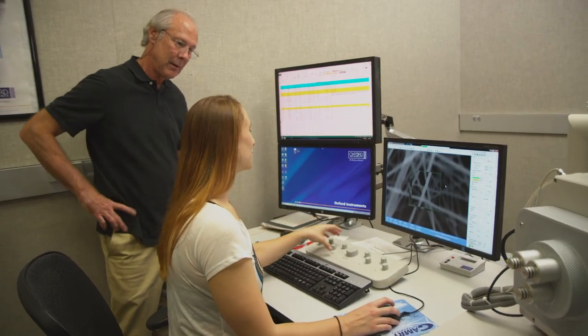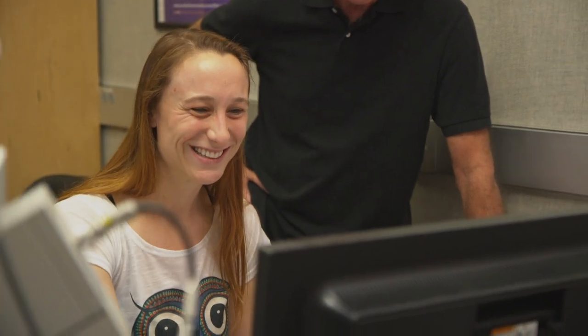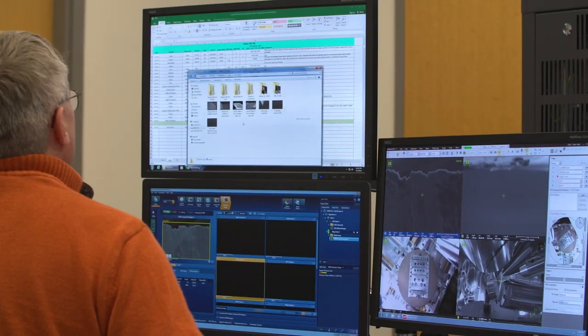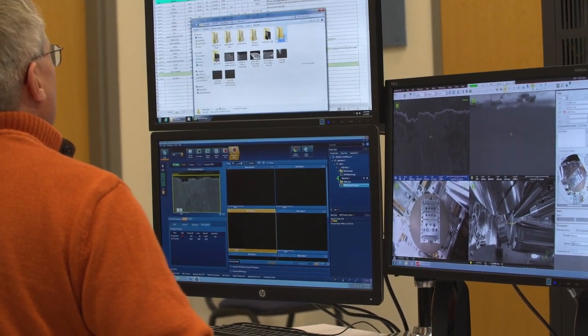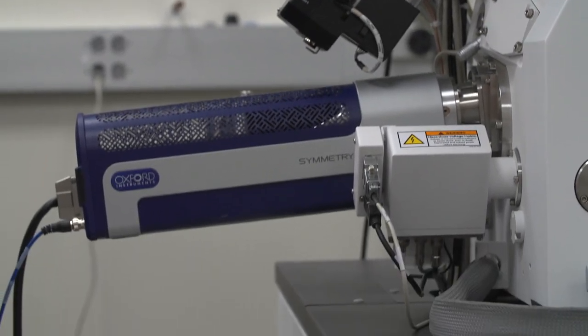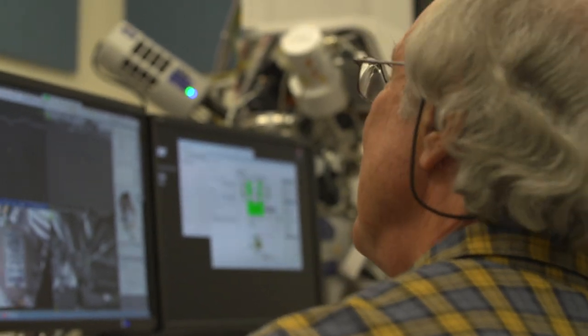In our other instruments like our XPS system or our focused ion beam system, they have standard capabilities but we've also chosen each of those to have very specific special capabilities. The focused ion beam system we have is combined with a scanning electron microscope column, and we're using it to process samples — milling materials away to modify devices, electronic devices to cut wires, to introduce wires to materials, and to prepare samples for transmission electron microscopy.